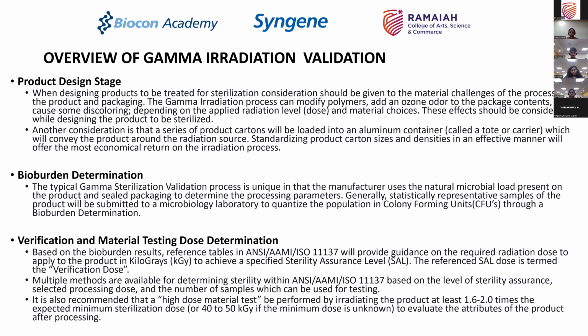Verification and material testing, dose determination. Now, based on the bioburden results, there are tables provided in ANSI ISO 11137 which will say that, okay, to achieve a specified sterility assurance level of 10 to the power of minus 6 or 10 to the power of minus 12, this is the amount of kilograys that you have to use. This is based on studies done globally before the ISO 11137 2006 guidelines were published, and those tables are available. These tables, of course, get updated over a period of time, and the updated tables are also available today.